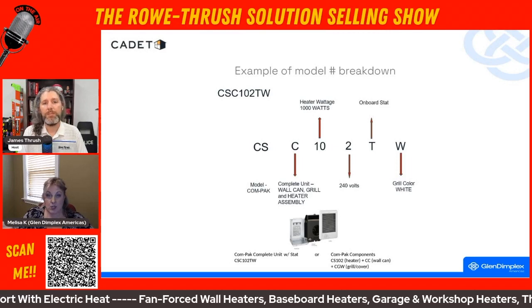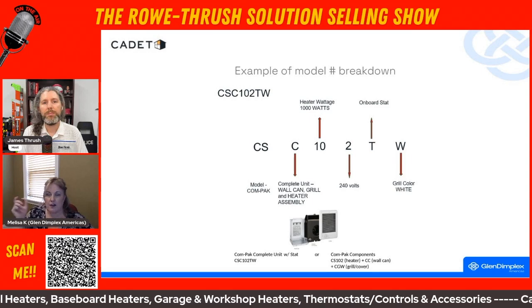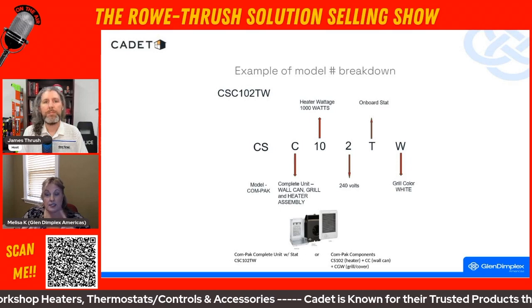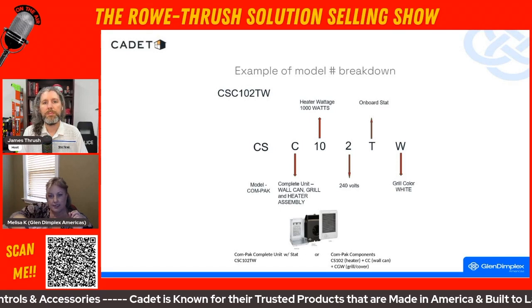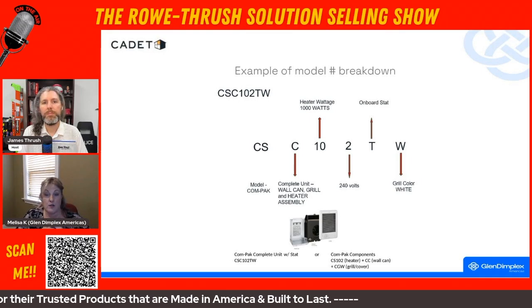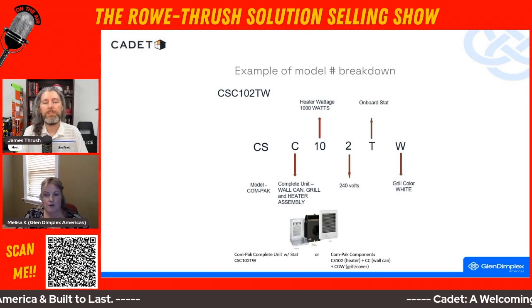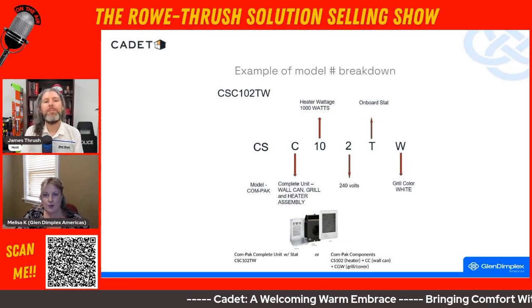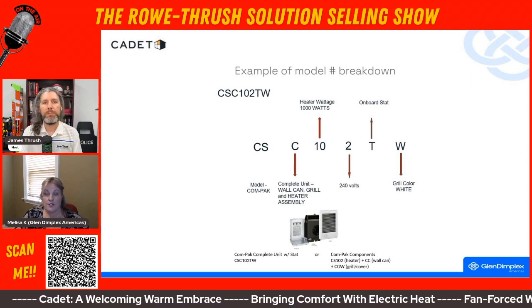Let's say you're standing in someone's shipping area and their heater doesn't work. Literally by taking that off, you can see what voltage it is and what wattage it is. If there is a 'T', the onboard thermostat is that dial — turning it on or off. But if they've got a wall thermostat, they would want one without a 'T' because they're running their heater off the wall thermostat. The 'W' is just the grill color, but it does help you do quick replacements and understand what they need.